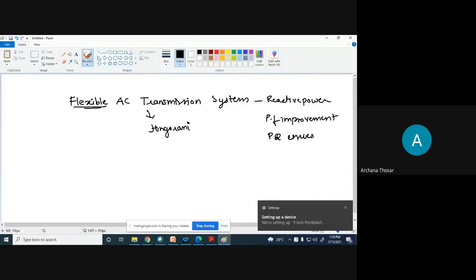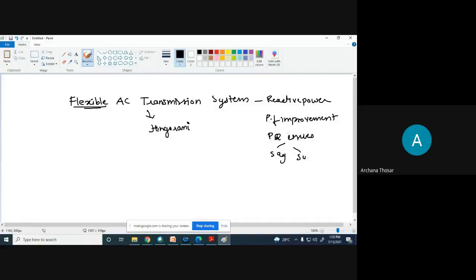So now we will start by setting up the context for why we should go for a flexible AC transmission system. It was introduced by Hingorani, the great researcher in power systems, and it can be used for reactive power compensation, power factor improvement, and dealing with power quality issues like sag and swell. Whenever there is a requirement of mitigating these issues, these FACTS controllers have proven very well, with good performance.